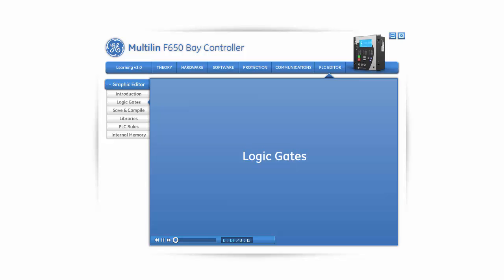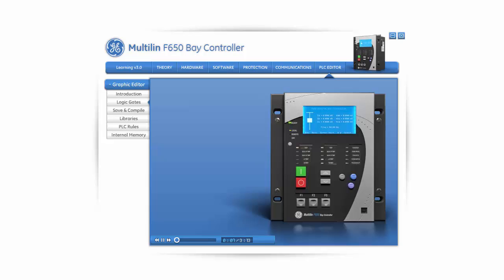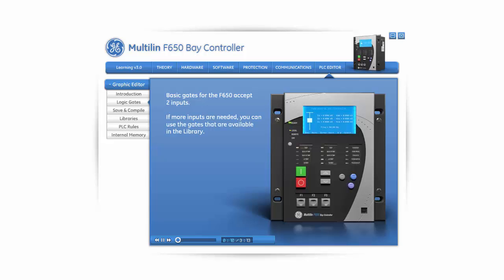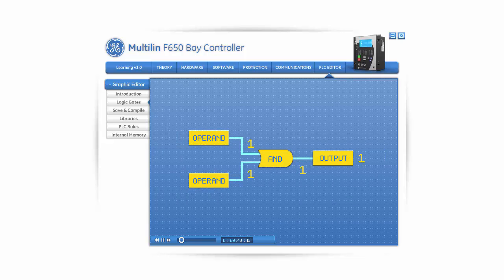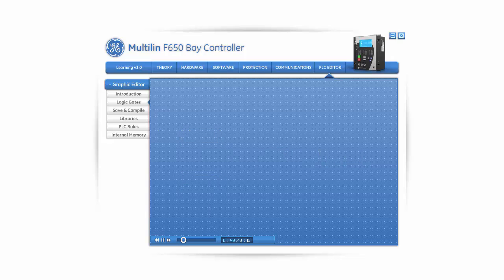In this section, we will learn about the different logic gates that can be used to program the F650 PLC logic editor. Basic gates for the F650 accept two inputs. If more inputs are needed, you can use the gates available in the library or create your own. An AND gate's output is ON, or a logic 1 state, only if all of its inputs are 1. If any of the inputs are 0, the output will be 0. An AND gate can be inserted by clicking on its icon and clicking again anywhere in the canvas.